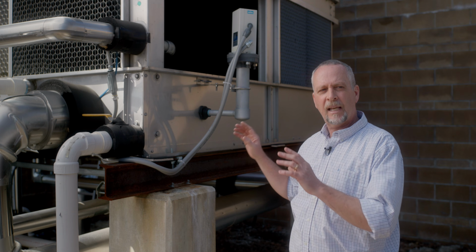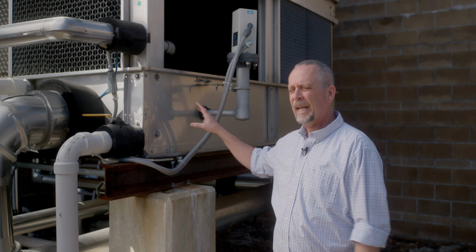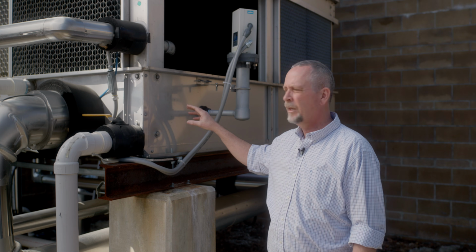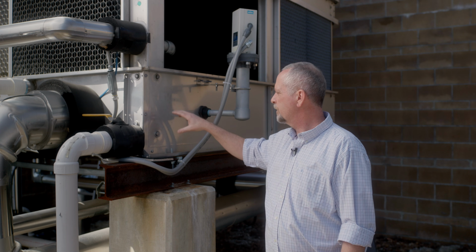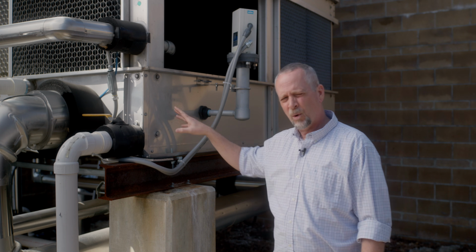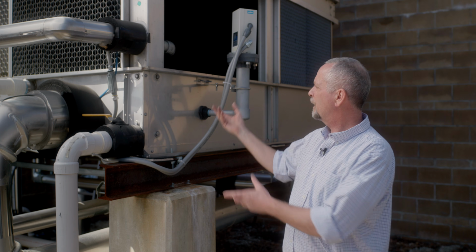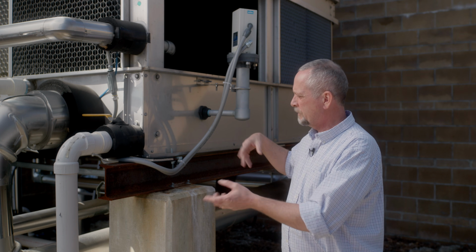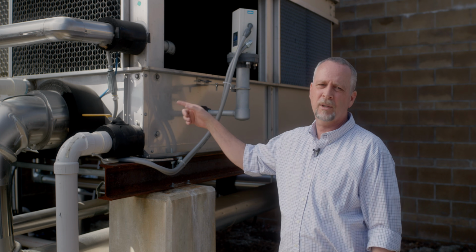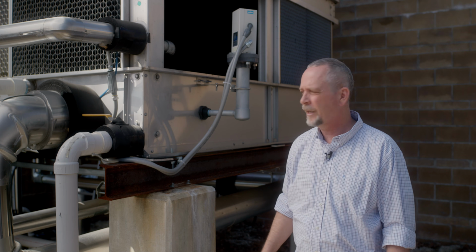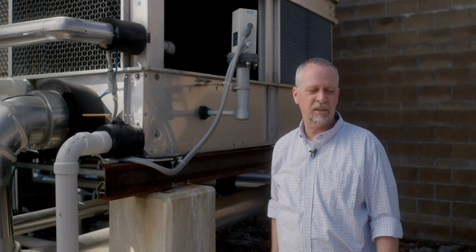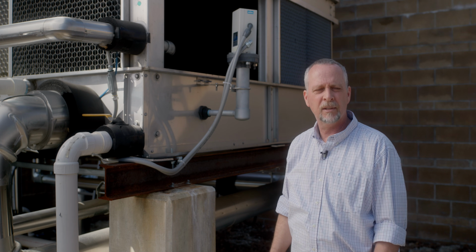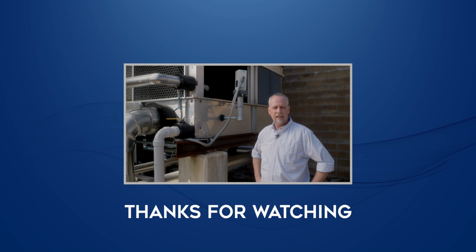And these are the things I always want to check when I'm doing my annual maintenance on my cooling tower, to make sure all these components function properly. And then if I'm doing a quarterly maintenance in the wintertime, I'm obviously not going to be draining the tower if I'm just doing a running inspection, but I always want to make sure my basin heater's operating as it should and my heat trace is functioning in the cold weather months. That'll save the customer a lot of headaches down the road.